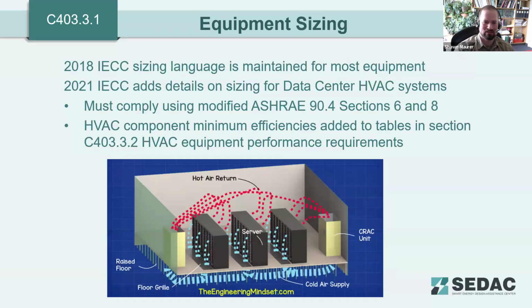And we really want to stress doing proper equipment sizing, because the typical standard is that equipment gets oversized, either based on rule of thumb estimates or conservative estimates. And that can result in equipment that doesn't cool properly, doesn't dehumidify properly, and doesn't achieve its efficiency ratings. So proper sizing is very, very important for HVAC systems.